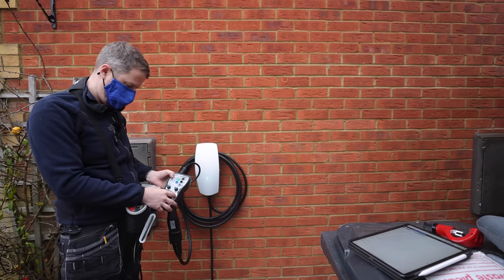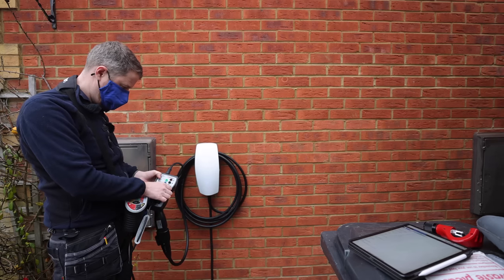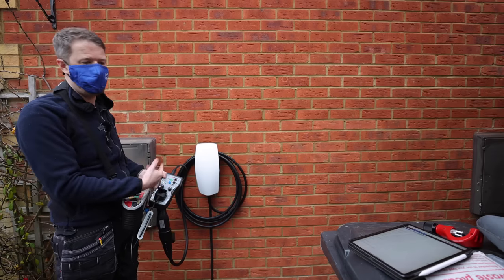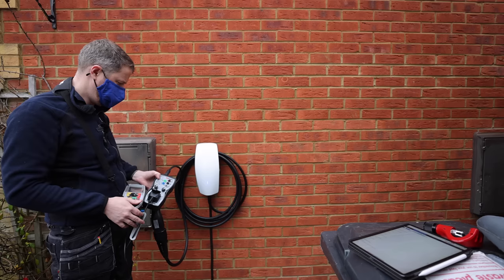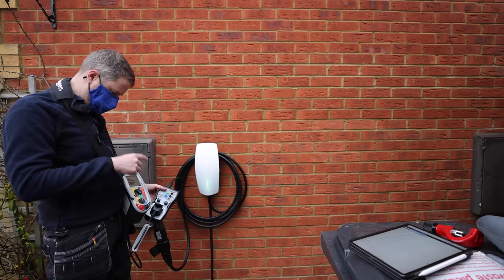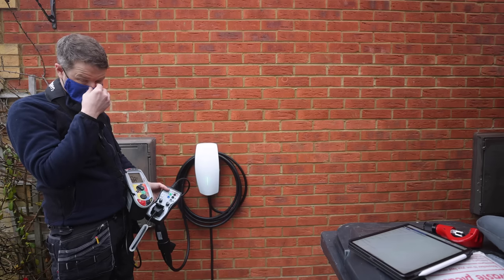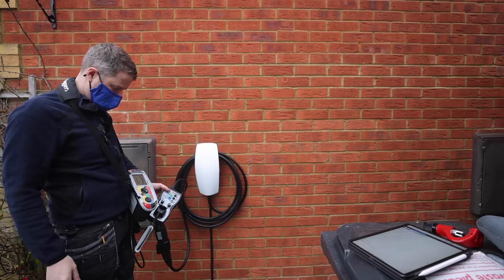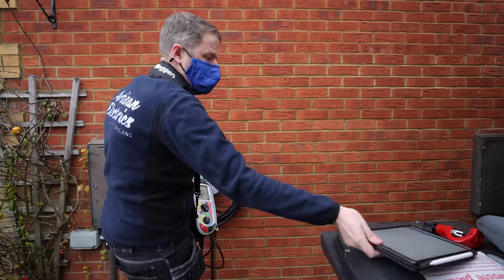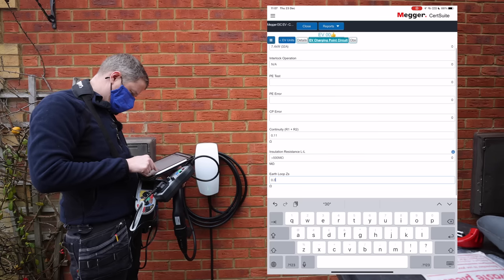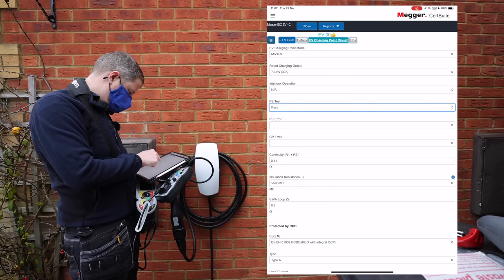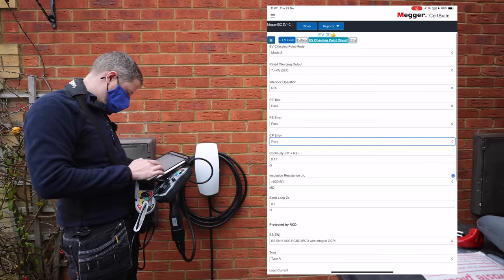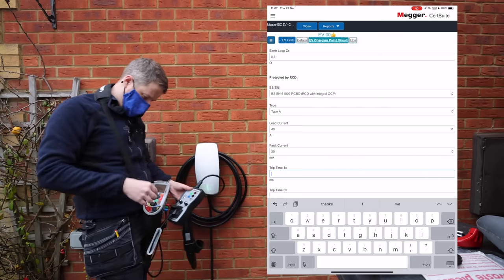And it's simulating a charge, we've got our Megger device doing that. So I've got to run through the various statuses, and to do that we use the CP state button. We set our PP state to 32 amps, which is the load that we're going to be using normally. So we've got various stages which change the lights in the tester. So that's on standby, that means it's plugged in but it's not charging. And then C is plugged in and charging, and that will click in in a minute. There we go, and it starts charging. We've got voltage now on our tester, and we can do a low resistance Zs test, earth loop impedance, and we get our earth loop impedance reading then on this.